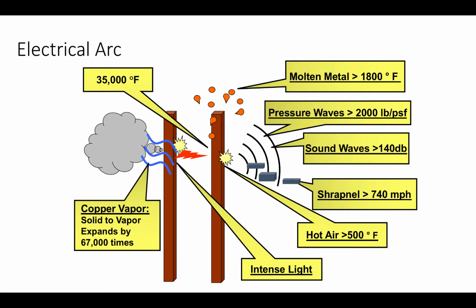An electrical arc can have a temperature of 35,000 degrees. There's nothing you can wear that will 100% stand up to that. The copper will actually melt and turn the solid copper to a vapor, and that expands by 67,000 times. You'll have intense light. The air temperature will be over 500 degrees. You will have shrapnel that can move at greater than 740 miles per hour. You can have sound waves that are over 140 decibels. In other words, it can bust your eardrums. Pressure waves can include over 2,000 pounds per square foot. And you'll have molten metal at over 1,800 degrees Fahrenheit. That's an example of what happens if there's an electrical arc.